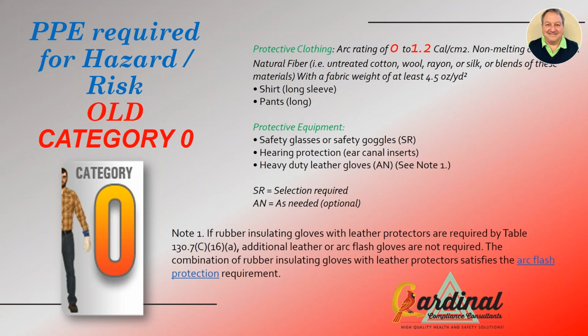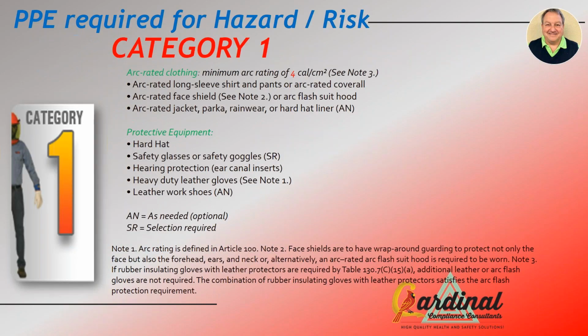Personal protective equipment. We used to have an older category called Category 0. And from this, it was sort of implied, oh, Category 0, it's no big deal. I can be safe. I can wear a cotton shirt, long sleeves, cotton pants, safety glasses, and I'm fine. But what happened is when you cross that arc flash barrier, you reach a point now where the arc flash energy is strong enough to cause a burn. So even the old Category 0 panels, if you got close enough to electrical conductors, you got a problem. That is, you had to remember to go up in category protection, and that would be Category 1.